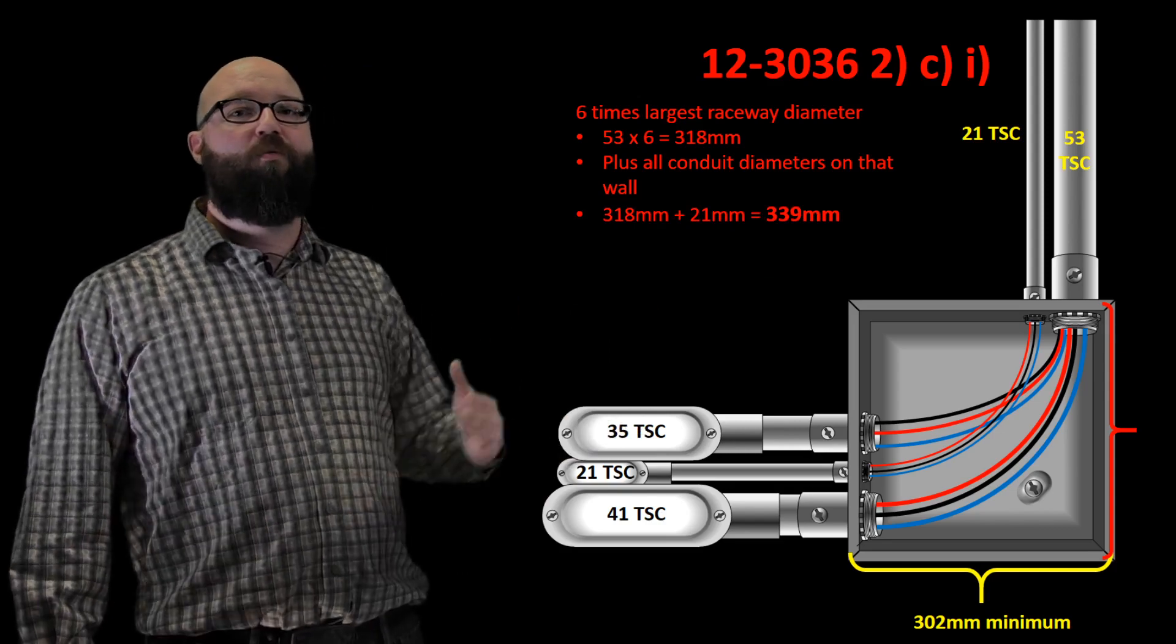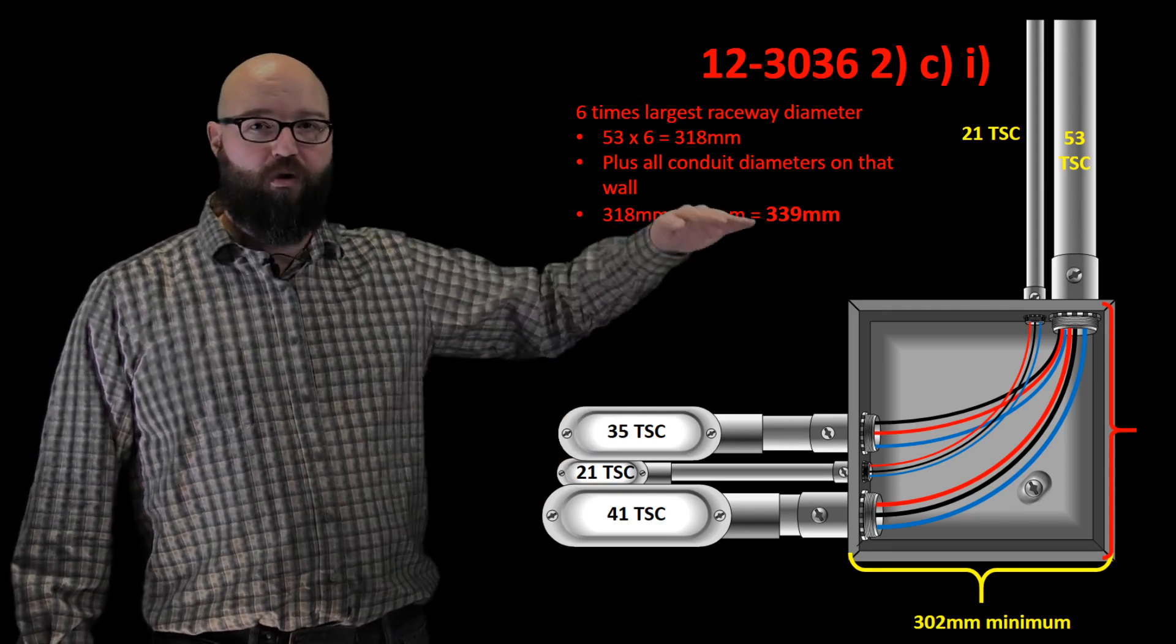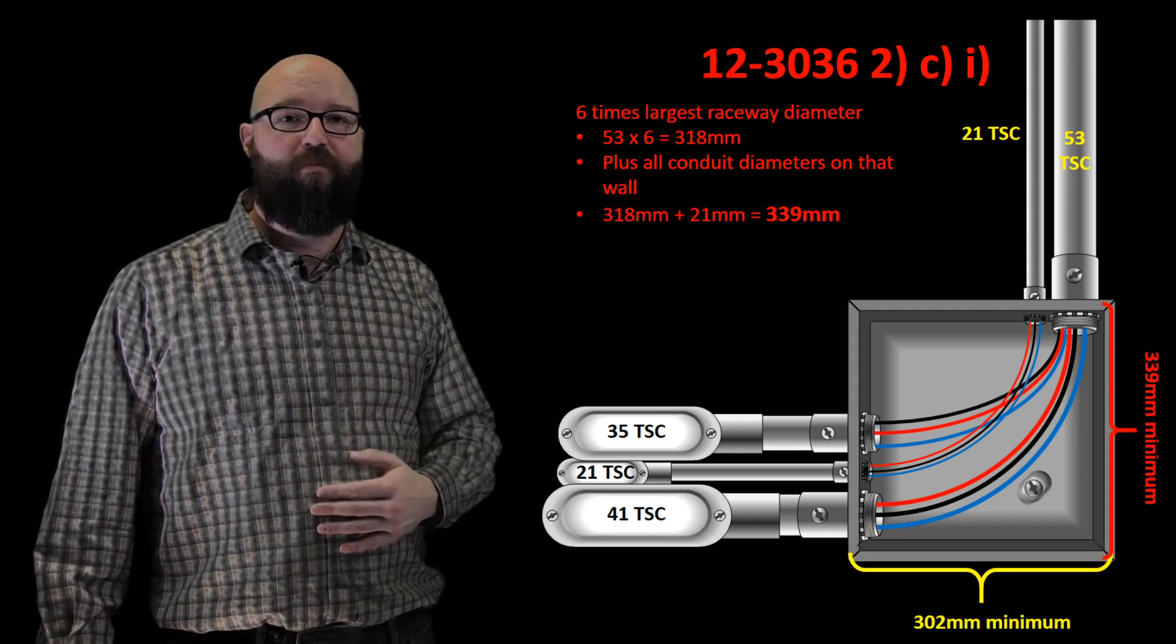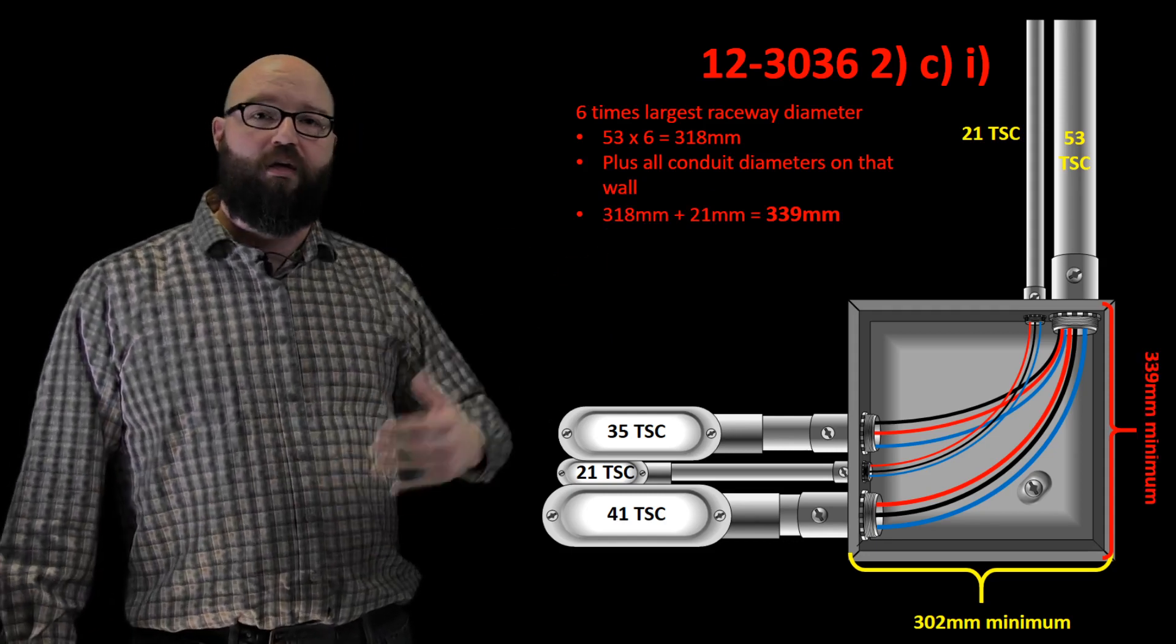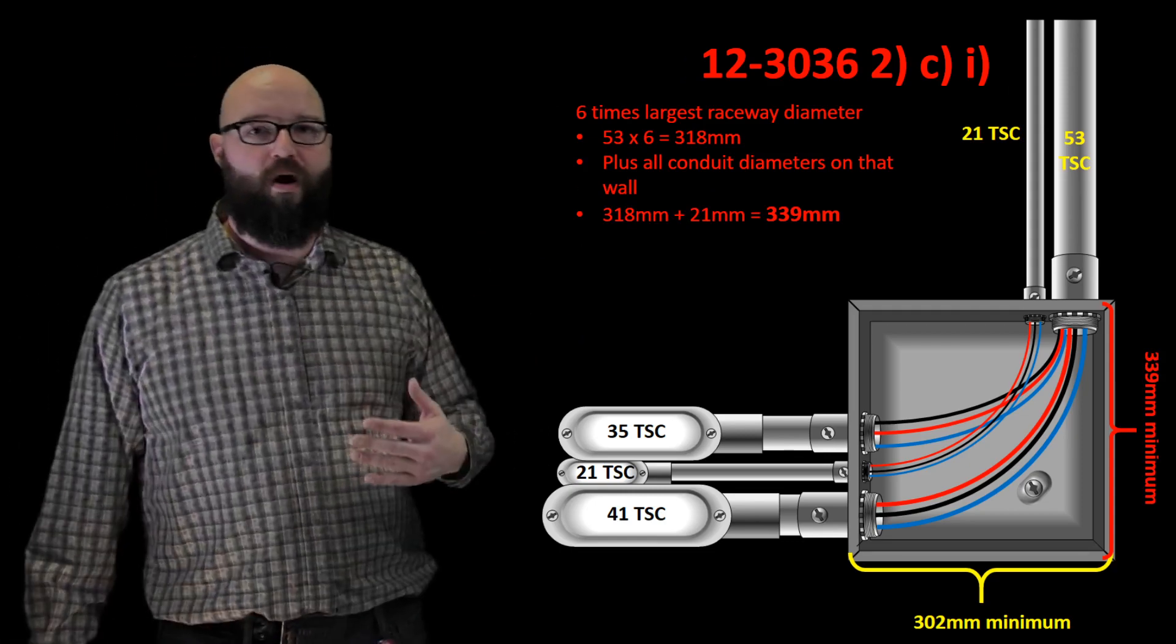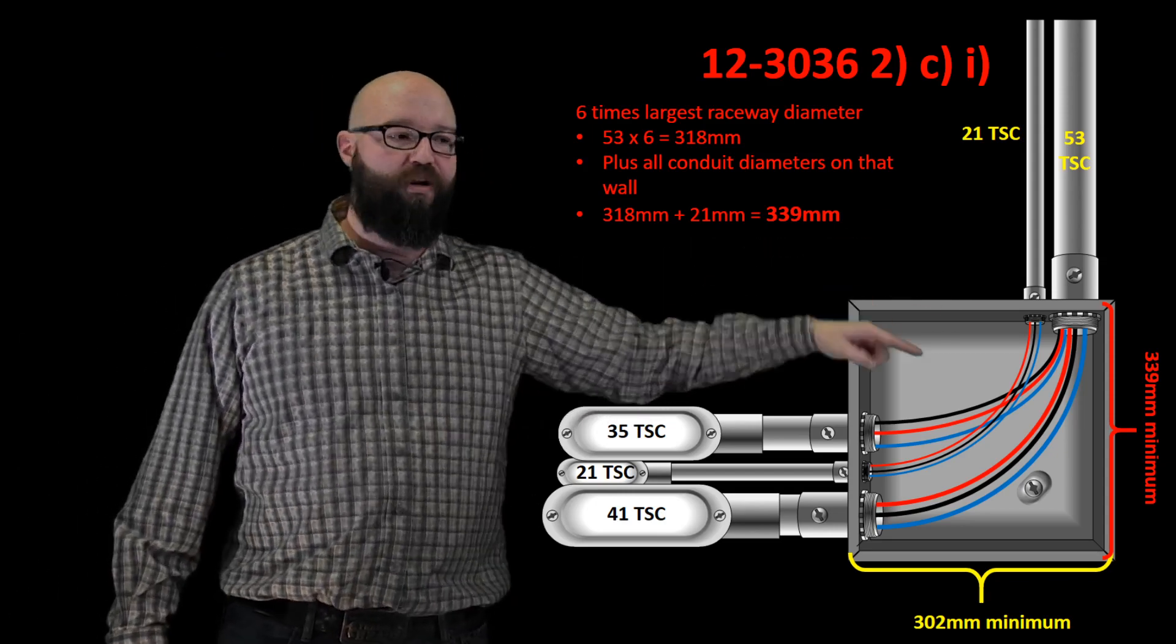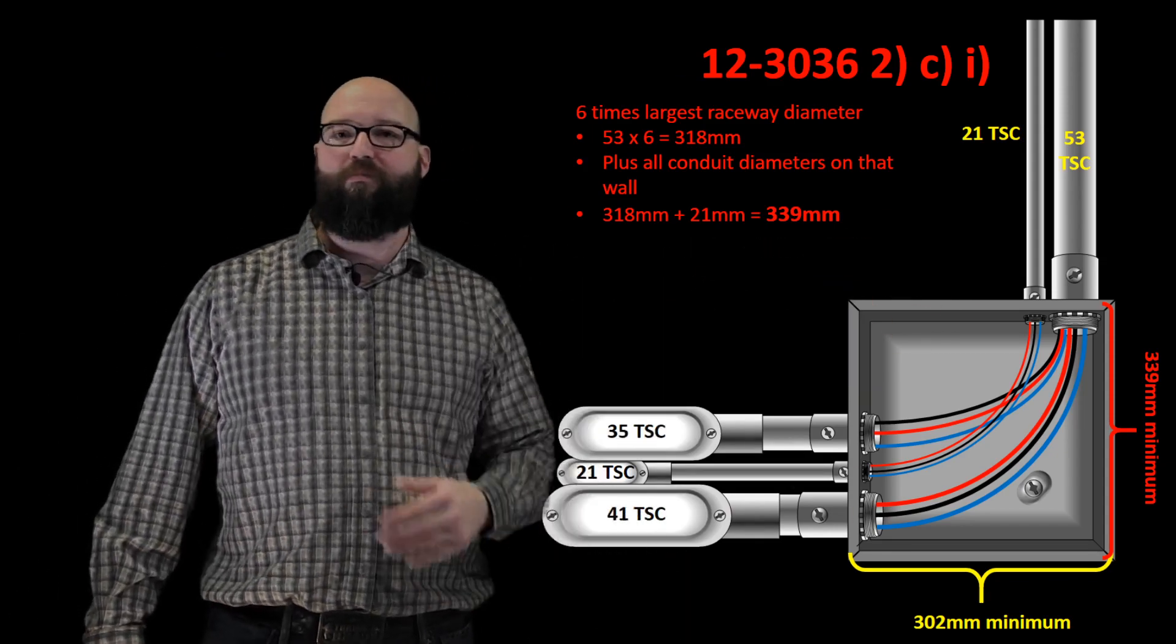When we're selecting our pull box, if we were going with a square, for example, this box would have to be a minimum 339 by 339 to follow 12-3036 properly. If we weren't going with a square, we could just say that the minimum dimension there would be 339 and the minimum dimension here would be 302.